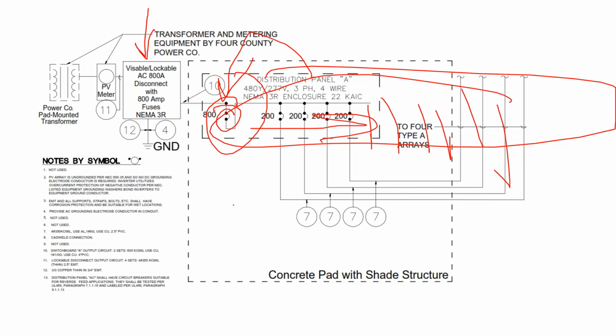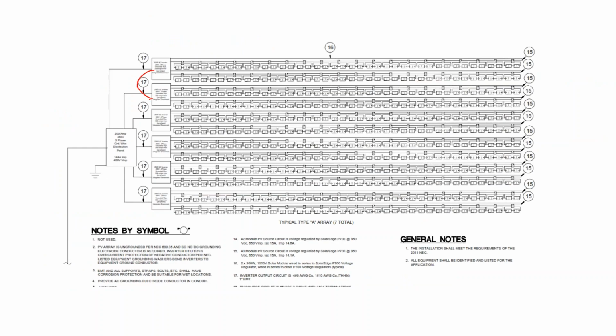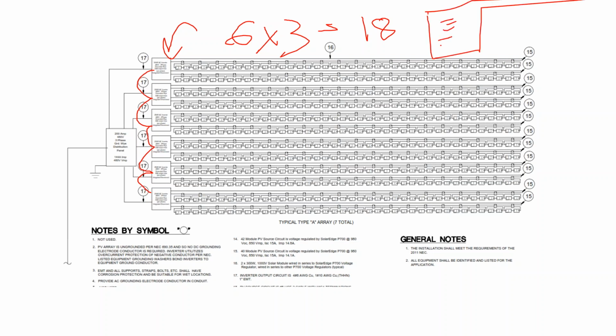And we see the reason why we have this main breaker here is because we have 7 inverters coming in. So here's our 7 inverters, 1, 2, 3, 4, 5. Oh, well, actually, this kind of got into our design here. This is a 3-phase electric service, and there's 6 inverters here. So each inverter is taking up 3 legs of power, and that means on a panel board that's about 18 switches. And you might be buying a panel board that could be 30 switches or 40 empty spots.